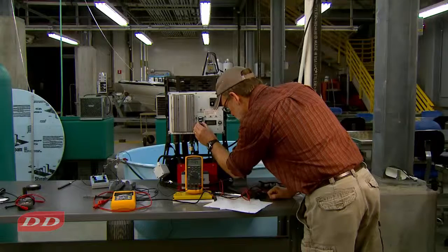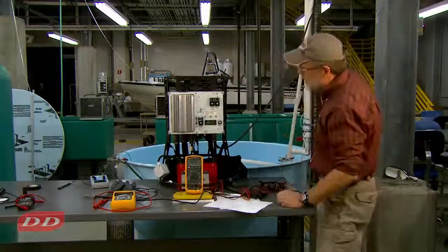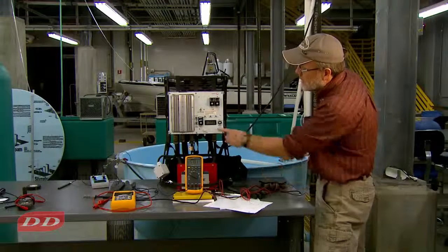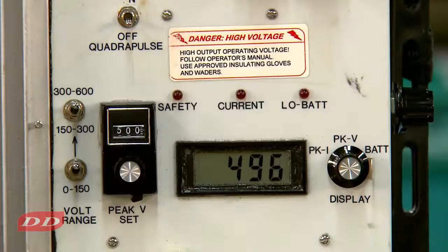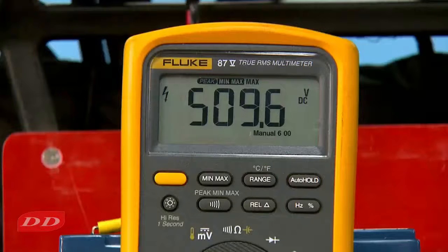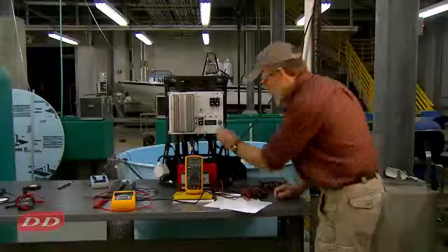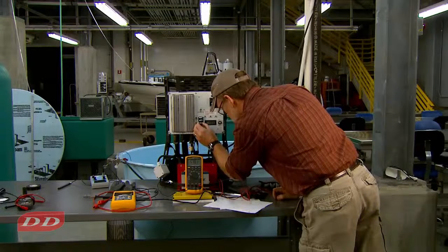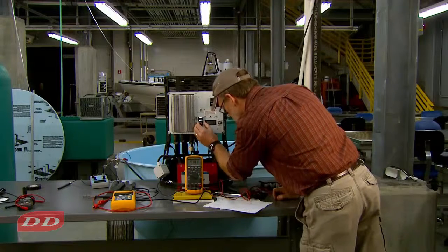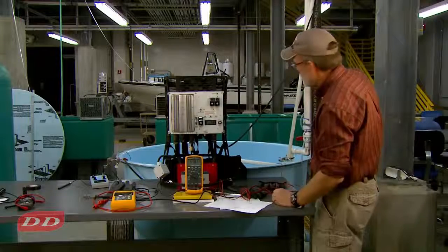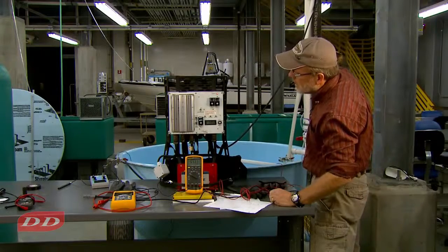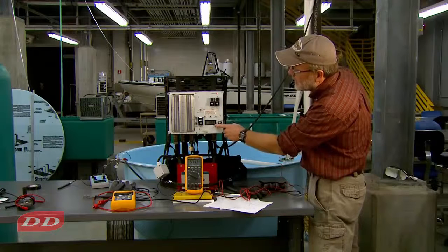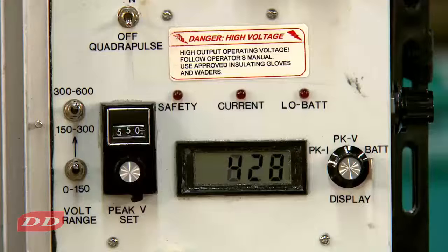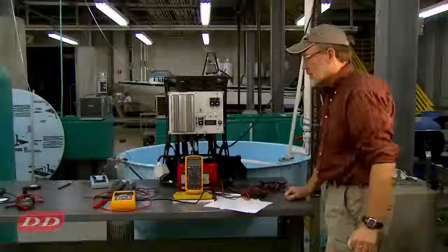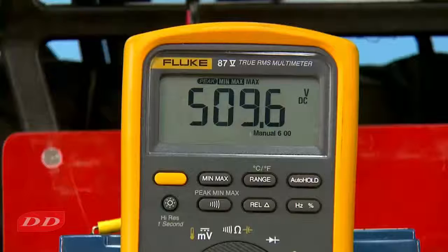We'll change now to 500 volts. Apply the electricity. Our reading on the voltmeter is about 499. On the multimeter, about 510. Again, good agreement. Now we'll increase to 550 volts. And our voltmeter says we're only getting about 496 or so volts, and our multimeter says about 511. So all pretty good agreement.